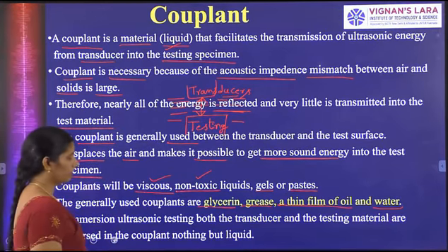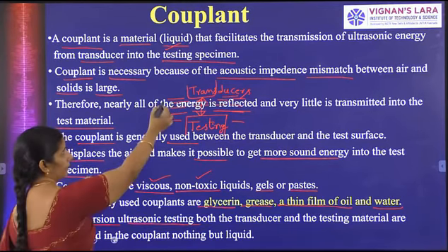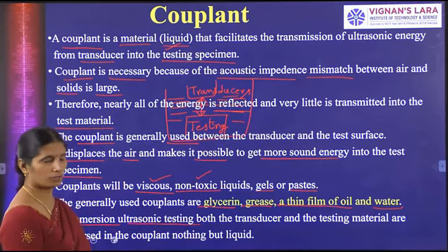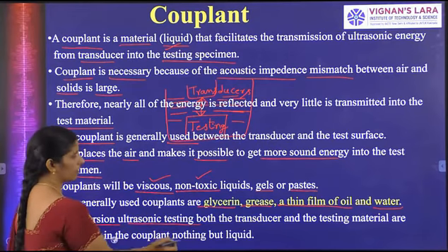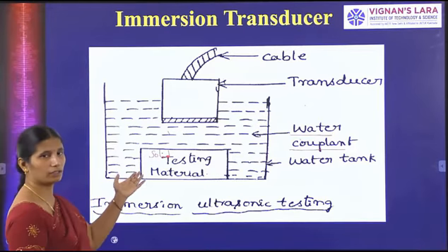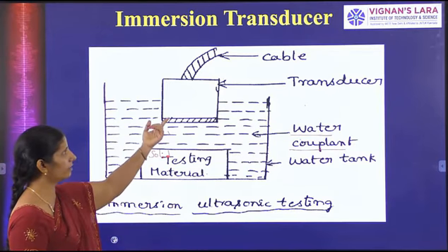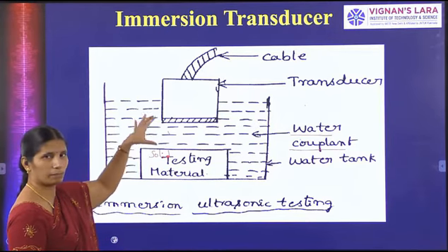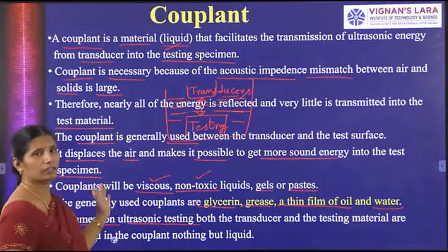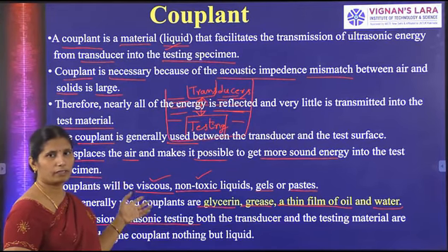In immersion ultrasonic testing, as we have observed in this diagram, both the transducer and the testing material are immersed in the couplant, which is nothing but the liquid. Then most of the ultrasonic energy will be passed through the testing material and the defects can be identified.